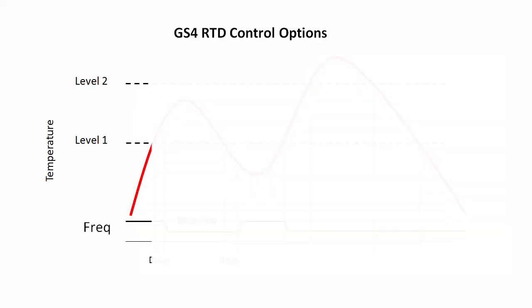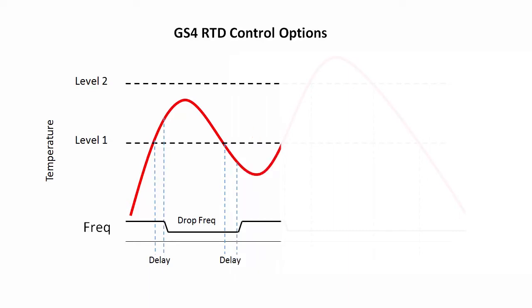When the temperature rises to level 1, which you specify, a delay timer starts. If the temperature is still above level 1 at the end of the delay, the GS4 can drop the motor speed to a value that you set. If the temperature falls back below level 1 for greater than the delay time, then the motor will resume normal operation.